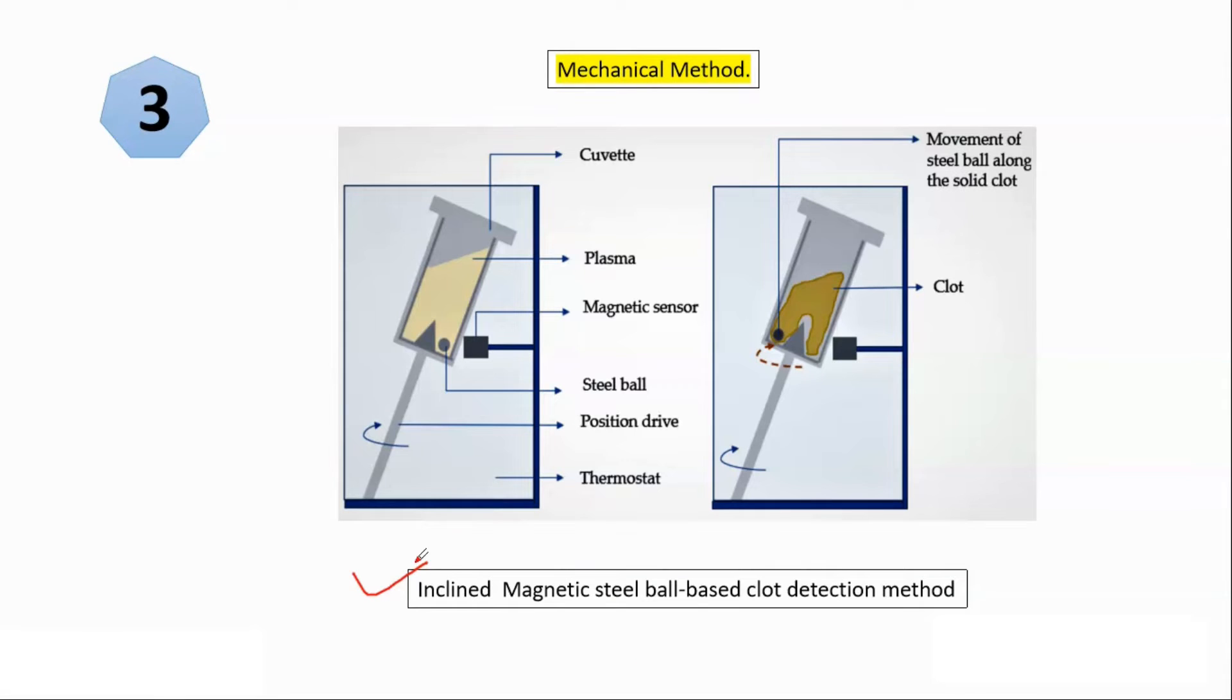So now move forward to other methods which are mechanical. So this is called inclined magnetic steel ball based clot detection method. It is most simplest one. Like here, this thing is rotating. This thing shows that whole instrument is rotating, whole cuvette holder or cuvette is rotating, but here steel ball is basically attracted to magnetic sensor.